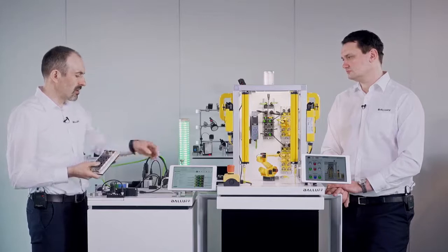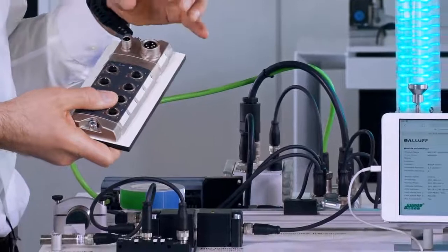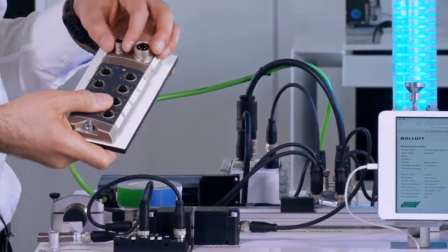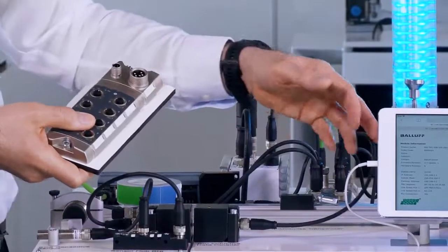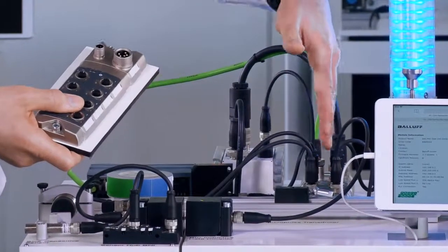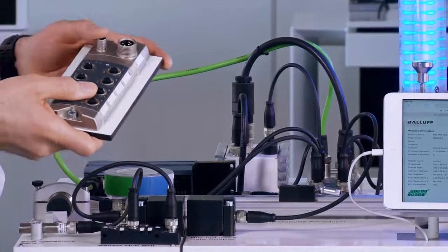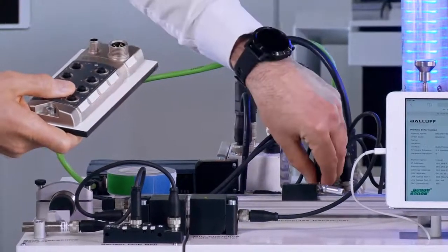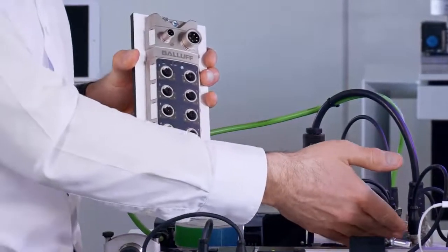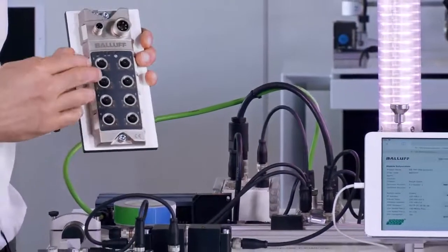What does it mean? In place of parallel wiring, or connecting an industrial network to each module, you can use this very simple 3-wire cable to connect to the IO-Link master, which is the main point in each network using IO-Link technology. On one port of such a module, you can connect the next IO module. So in place of 2 signals, which was possible to connect only to this module, you can connect up to 16 signals to such a module.